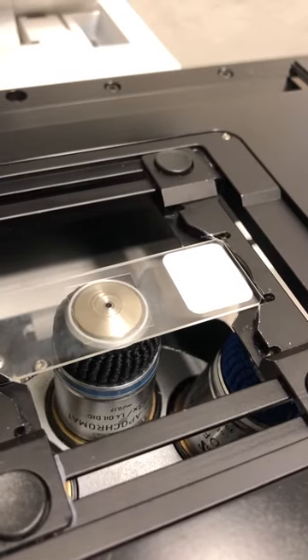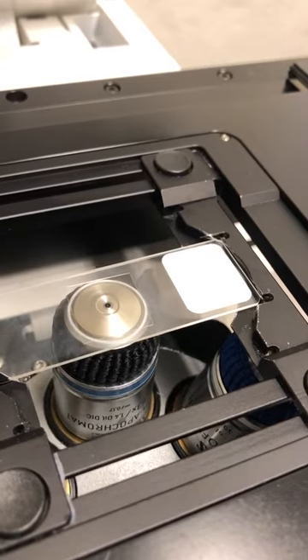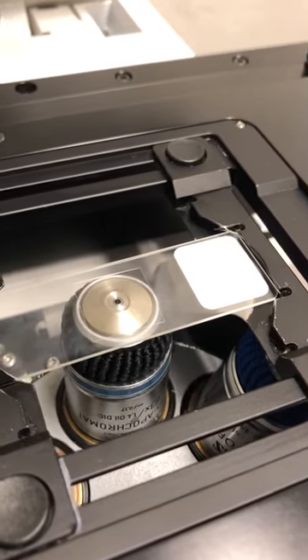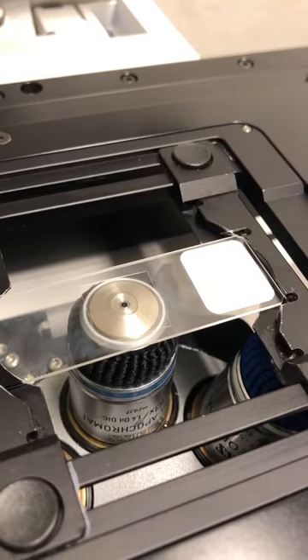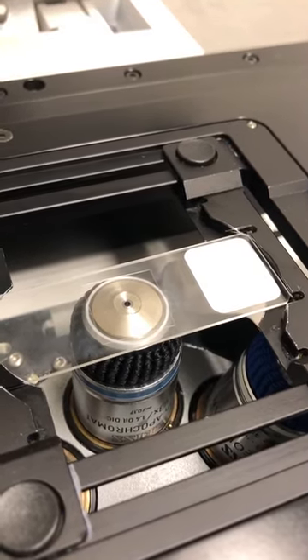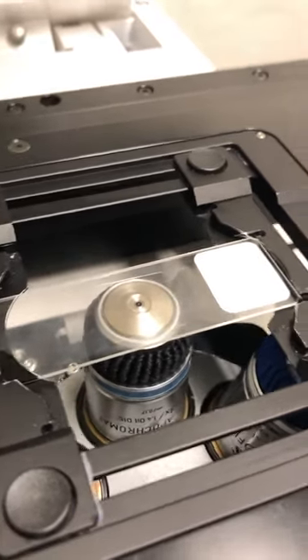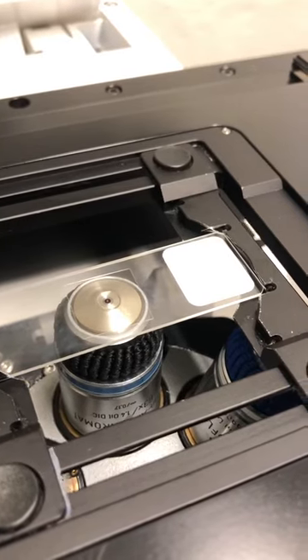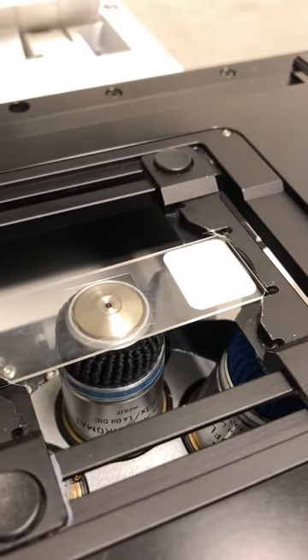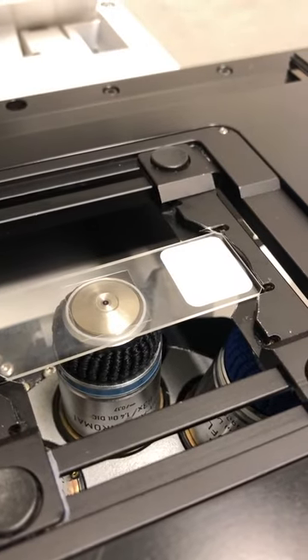You can see the oil touch the sample. You can tell because if I move the focus knob towards me the oil slick gets smaller, meaning the objective is going down. If I move it away from me the oil slick gets bigger. Once you see the oil slick, move a little bit down — you want to be below your sample when focusing so that moving away from you means you're going into the sample. I'll focus by eye and return to the confocal software once that's done.